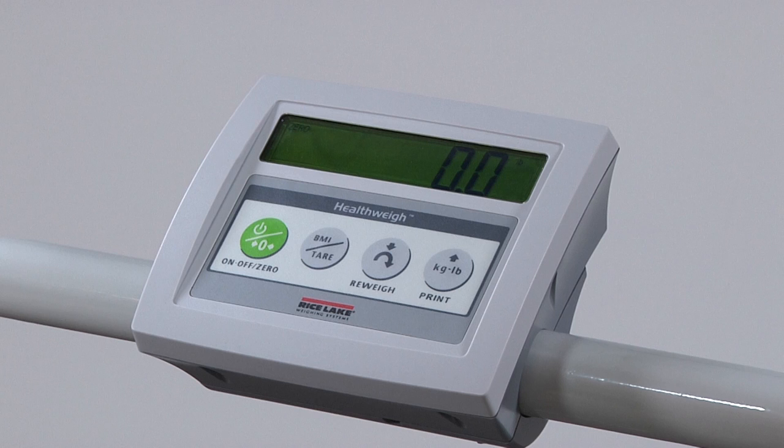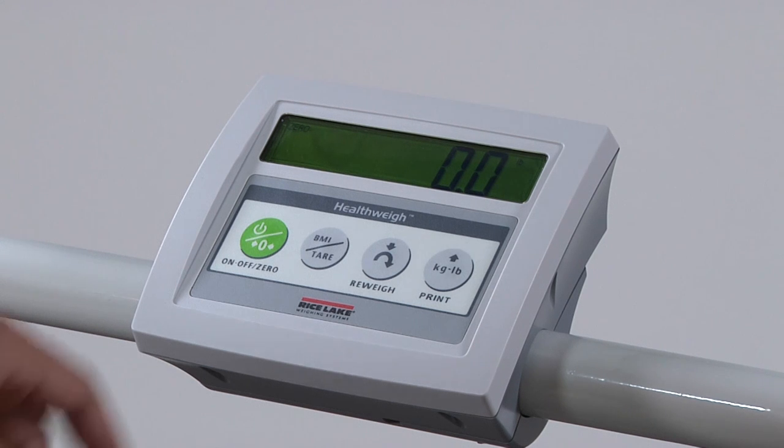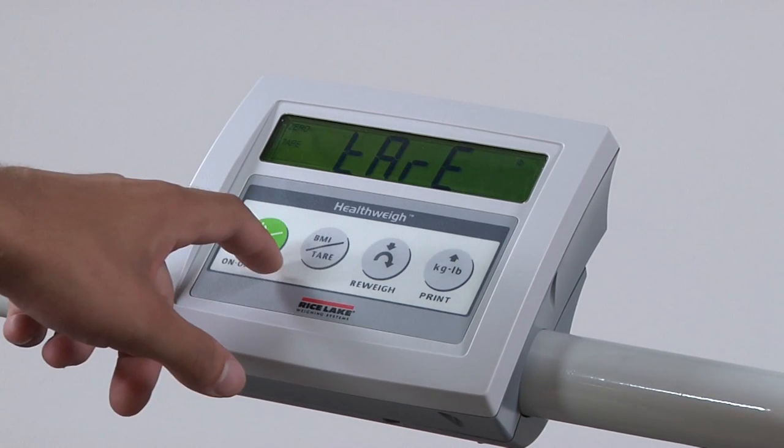Many times the weight of a wheelchair is already known. Enter the value as follows. Without any weight on the scale, lightly press and release the tare key. Because the keypad is attached to a live portion of the scale, a light touch is all that is required. Adding too much pressure may cause the scale to begin a weight reading.